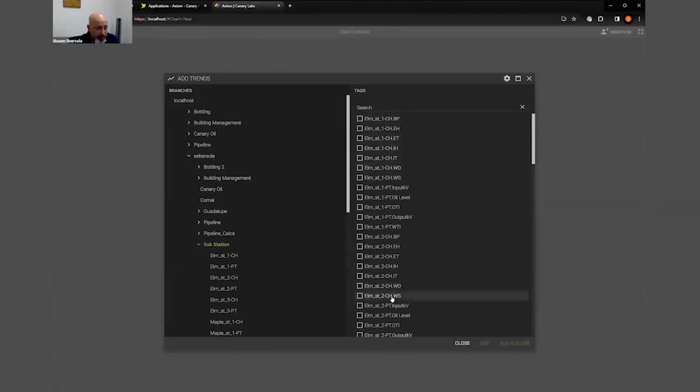We recommend no more than 25,000 tags per data set. You can go over that, but that's really the limit we recommend. There is no limit, though, to the number of data sets that you have in your historian. And Clark may have mentioned it, but in the historian itself, you can store more than 2 million tags.